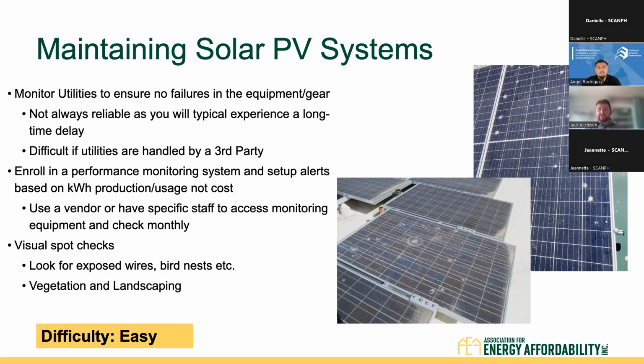Use a vendor or have a specific staff person to access the monitoring equipment and check it monthly. Ultimately, if you don't have a specific staff person, what can happen is people aren't familiar with what they're looking at, and they aren't comparing it to the previous month. So having a specific staff person dedicated to reviewing that monitoring data is really your best approach. And then maintenance staff should be doing visual spot checks, looking for exposed wires, bird nests, squirrels, that sort of thing. And then vegetation and landscaping: you want to avoid vegetation and landscaping shading the panels. So you want to work with your landscaper to make sure they're trimming back trees to ensure your panels are getting full sun when they have the opportunity to.